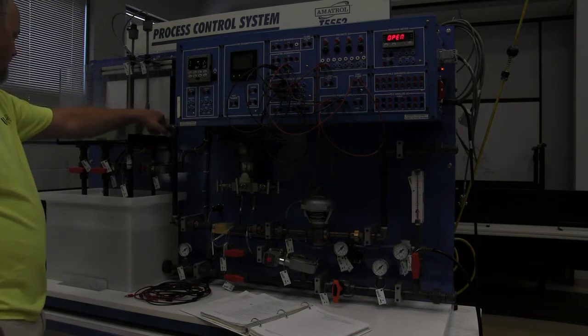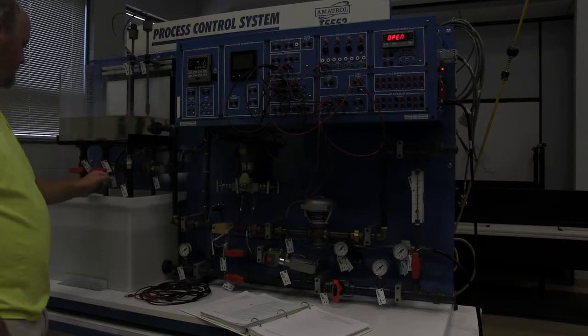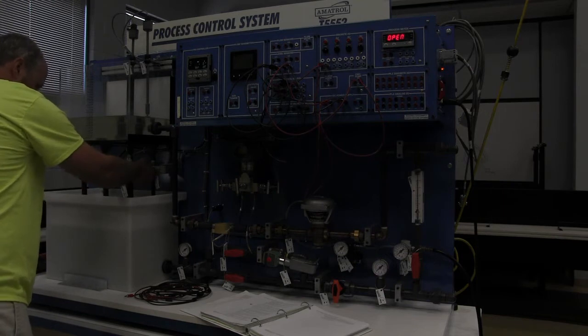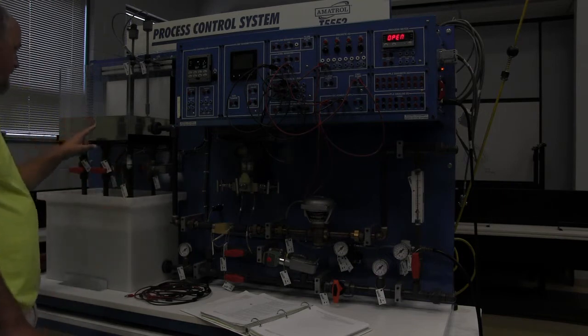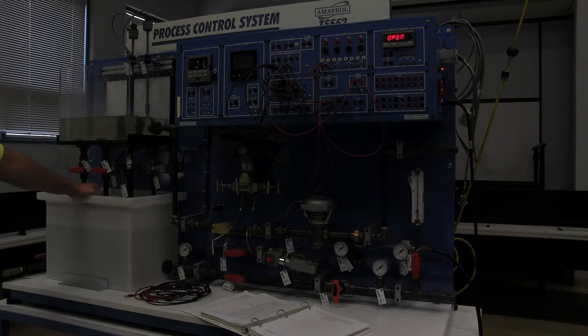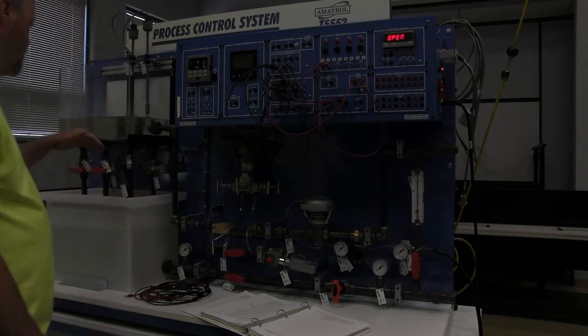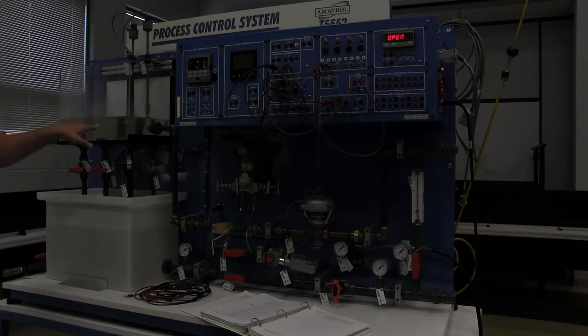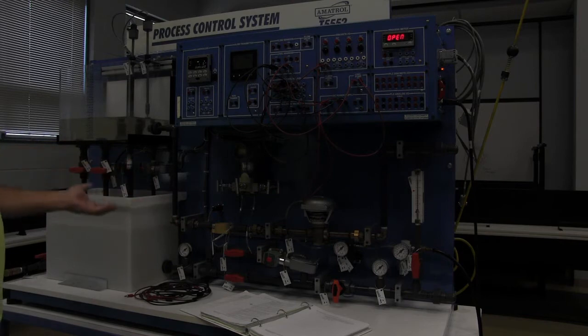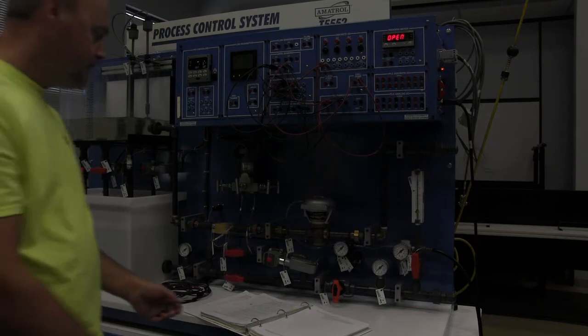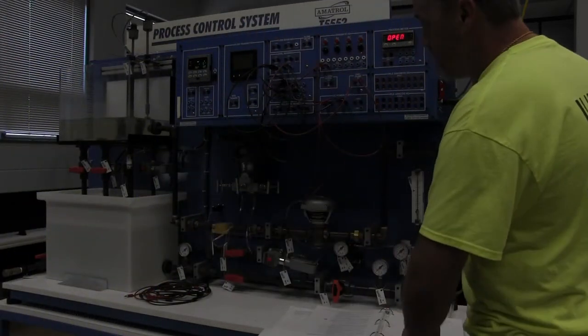When it shut off, it opened the solenoid valve here, which is draining the tank back down. It's a smaller pipe, so it doesn't drain as fast, but the level is dropping. Once the level drops, so the second float is down, it will then close the solenoid valve, turn the pump back on, and fill the tank back up. And I'll step off to the side so you guys can watch that.